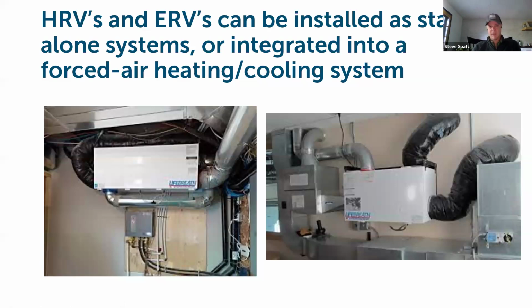My opinion, ideally, there would be two separate duct systems if you are in that situation. One, your heating and cooling system is its own thing, and the ventilation system has its own duct system connected directly to the HRV or ERV. The reason I say this is because, just equipment-wise, we're talking about two entirely different needs for the duct design, where the ERV or HRV is moving less air at a lower volume and different static pressures through different duct diameters, whereas a forced air heating and cooling system is moving air in a different manner.